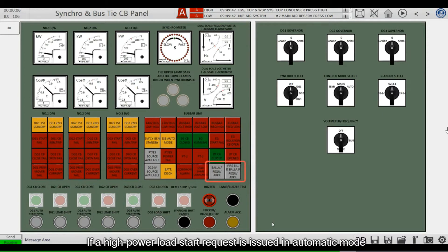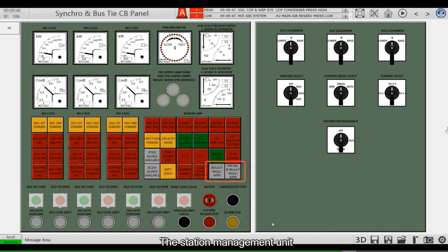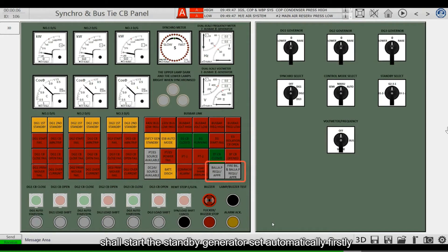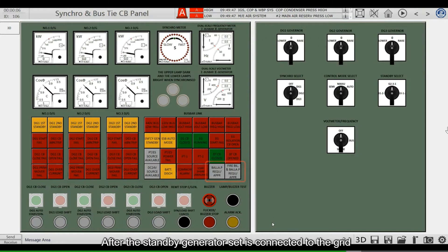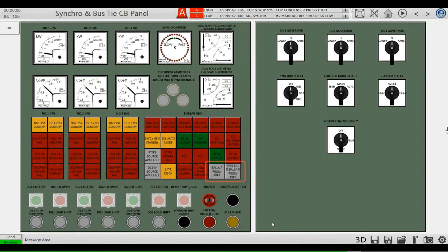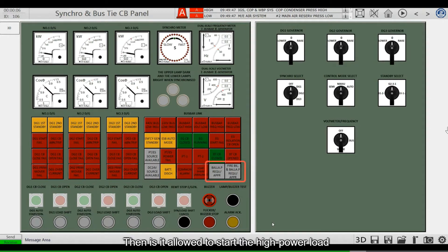If a high power load start request is issued in automatic mode, the power station management unit will start the standby generator set automatically first. After the standby generator set is connected to the grid and the power margin is sufficient, it is then allowed to start the high power load.